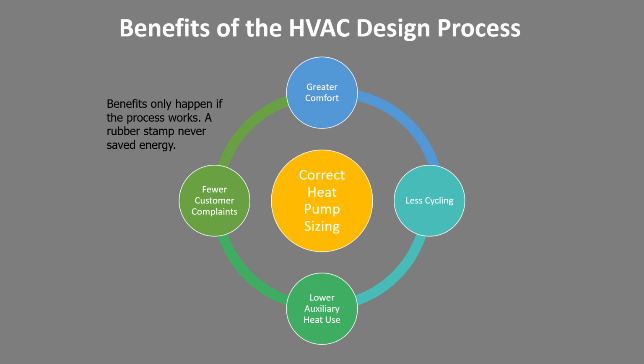Benefits of the HVAC design process. Well, they don't happen by themselves, so we have to do some planning. Basically, if we get the right size heat pump, homeowners will experience greater levels of comfort. The unit will cycle less, which is easier on the compressor. Lots of lower auxiliary heat use, and that's a good thing. When that auxiliary heat comes on, that's when the meter really starts to spin. Fewer customer complaints, fewer go-backs to the home on our own time.